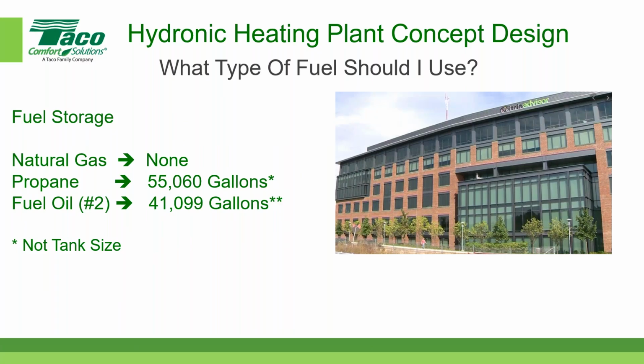And I put this note in here, not the tank size. So in other words, propane is 55,060 gallons. That does not mean that you would select a propane tank of approximately 55 or 60,000 gallons, because the propane has to have a certain amount of surface area so that it evaporates properly to supply the boilers with the right amount of propane.